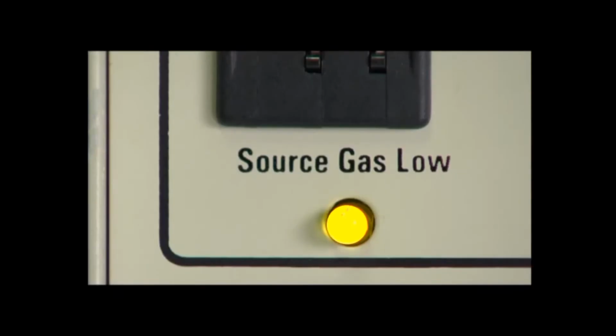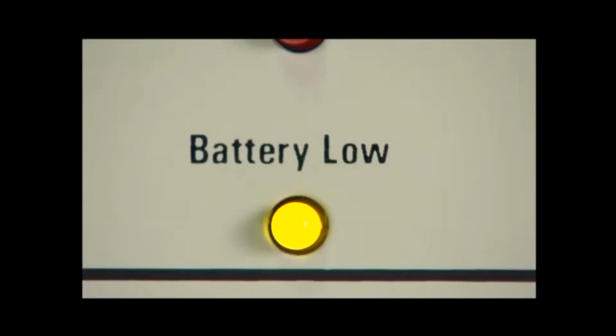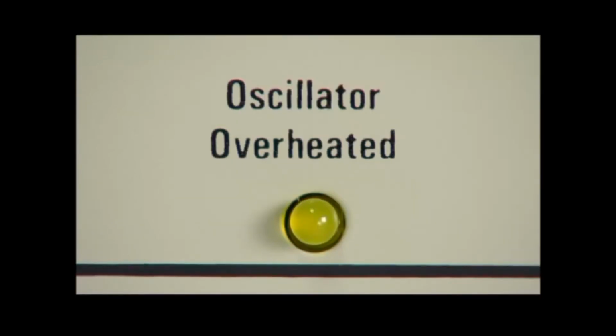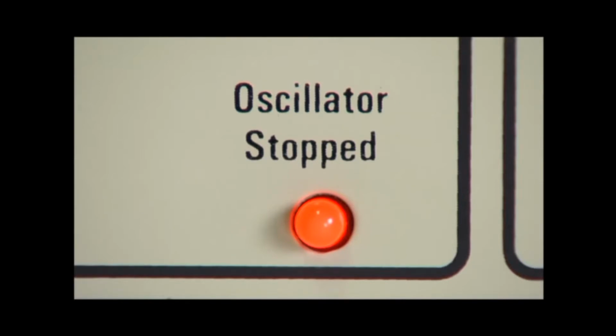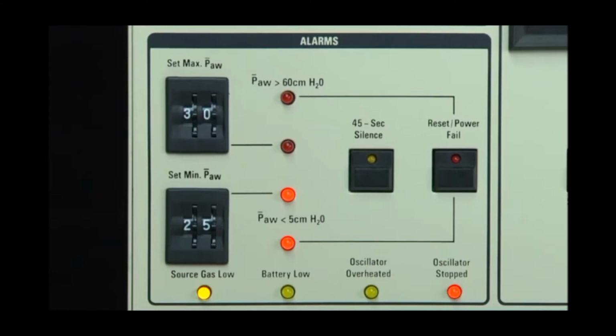This LED indicates a low source gas condition of less than 30 psi for either of the high-pressure gas inlets. The battery low LED means that the power failure alarm battery located in the rear panel of the ventilator must be changed. The oscillator overheated LED signals that the internal oscillator coil temperature has reached approximately 150 degrees Celsius. The oscillator stopped indicator means that the oscillator system is enabled, but the amplitude is less than or equal to 7 centimeters of water pressure. An audible tone will accompany this red indicator and will automatically reset once the alarm condition no longer exists.